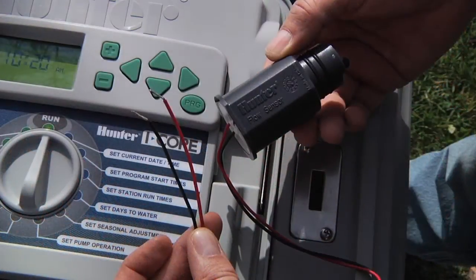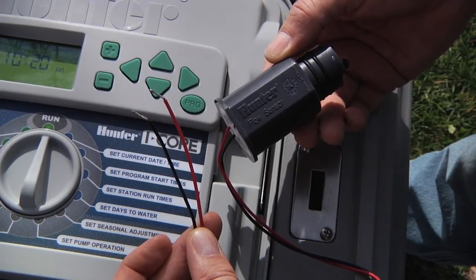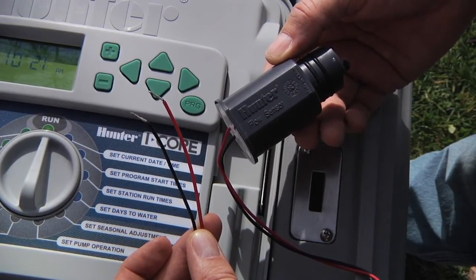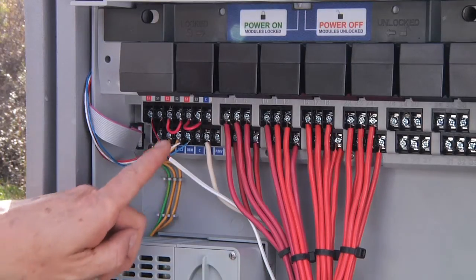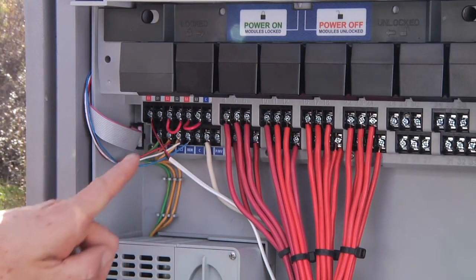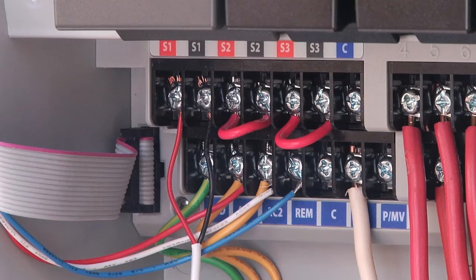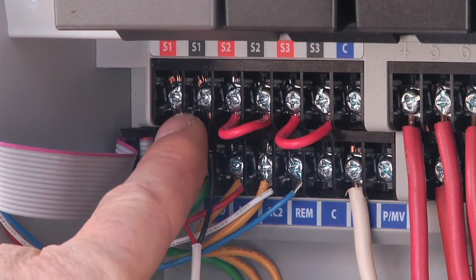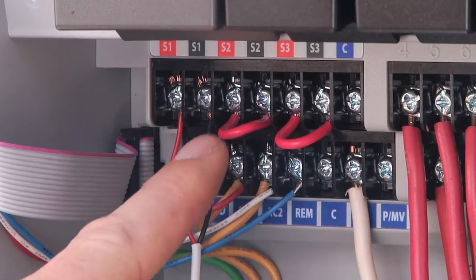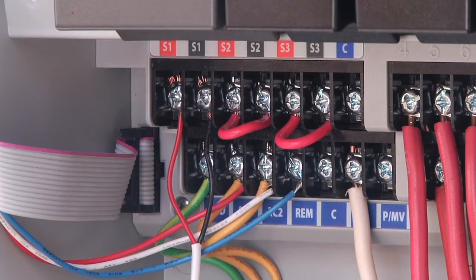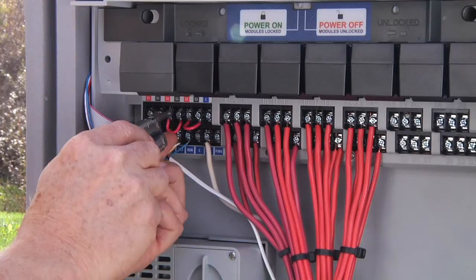configuring the sensor. The flow sensor is connected directly to the controller through a pair of wires, a red and a black one. When connecting a sensor, it is important that you remove the jumper wire that connects the two screws. Also, when no sensor is connected, the jumper must be in place. The sensor wires are routed to a set of sensor terminals in the wiring compartment, either S1 or S2.